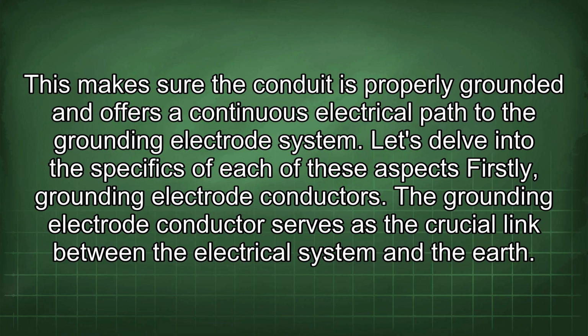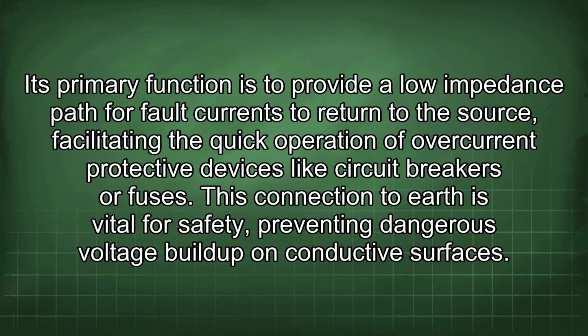Firstly, grounding electrode conductors. The grounding electrode conductor serves as the crucial link between the electrical system and the earth. Its primary function is to provide a low impedance path for fault currents to return to the source, facilitating the quick operation of overcurrent protective devices like circuit breakers or fuses. This connection to earth is vital for safety, preventing dangerous voltage buildup on conductive surfaces.